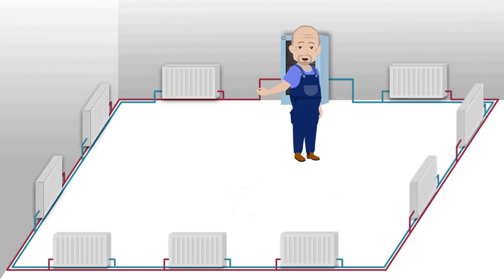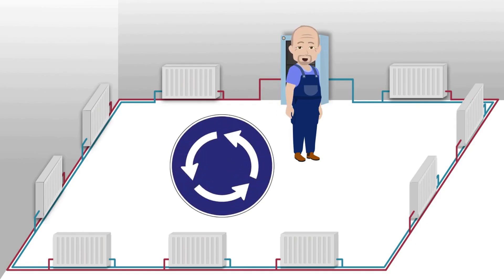This leads to an even heating of the radiators, even those further away from the boiler. To make it clearer, imagine it's like traffic flow. It's like a bypass with no lights and no 180-degree turns. There is no need to regulate the flow, as it regulates itself.